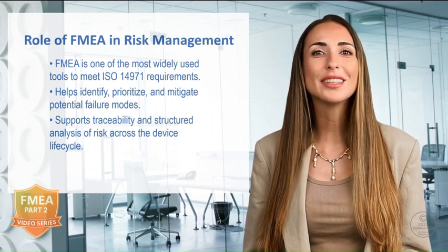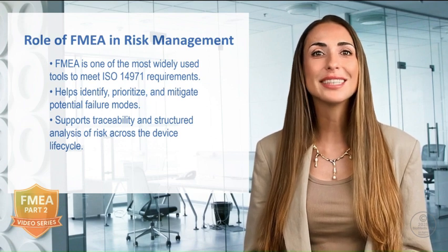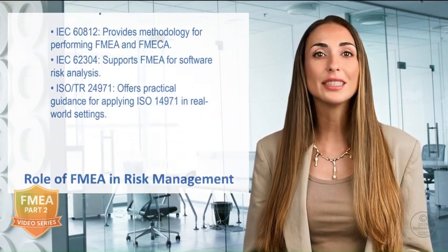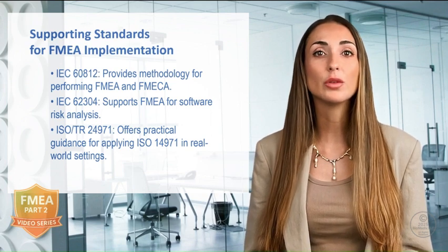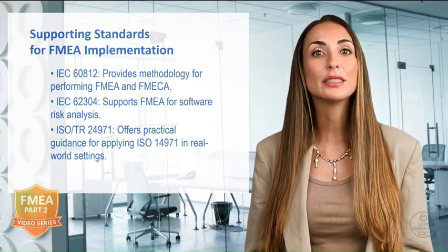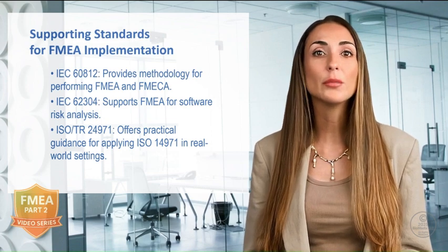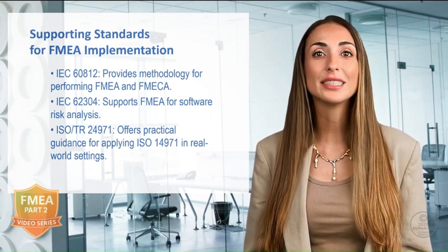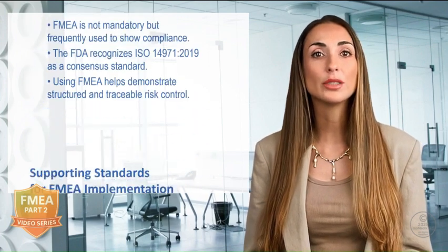One of the most widely used tools within this framework is FMEA. And for teams seeking detailed methodology, IEC 60812 offers formal guidance on how to conduct both FMEA and the more advanced FMECA. When it comes to medical device software, the application of FMEA is further supported by IEC 62304, the International Standard for Software Lifecycle Processes.